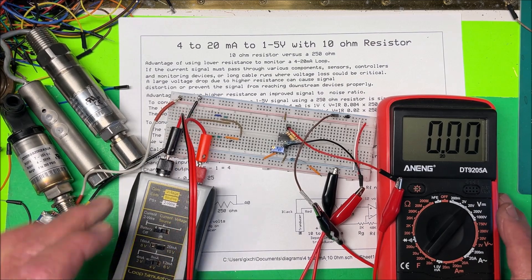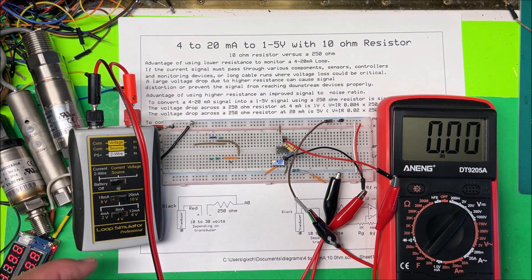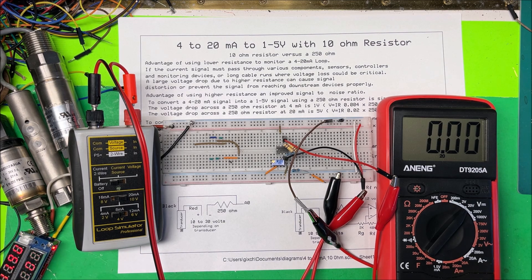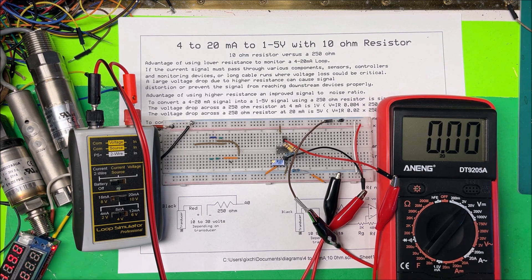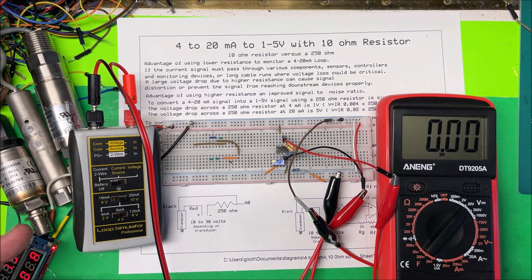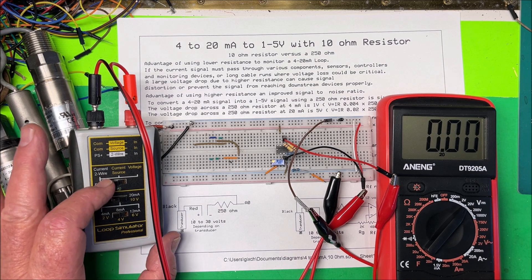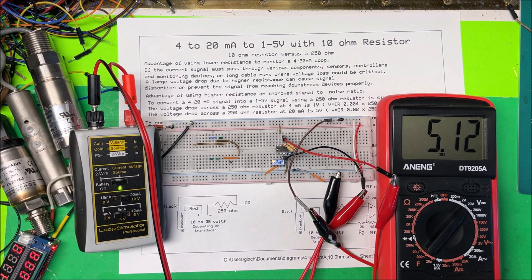And what I have here is a loop simulator. We use that to test these loops. It puts out current or voltage, or you can use it as a two-wire loop there. So I'm going to put it on 20 milliamps current source.